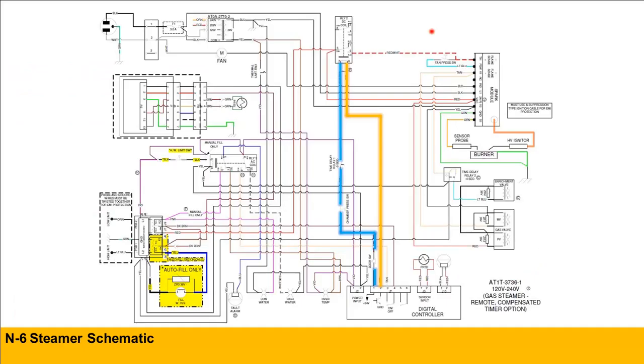All right, so once again, we're still at a steamer. It's not heating. Now, we're going to focus on the DC circuit because when we first turned it on, we had static pressure on a manometer, and we also got a brief flash from the ignition module. At this point, I know that circuit is good. I'm not going to worry about it. So now I'm going to focus on the DC circuit. As Dan stated, voltage is rectified into 24 volts DC. We have our ground, which is our orange wire highlighted, and the wire is actually orange, going to the negative on the DC relay. But once again, everything starts at the control board.